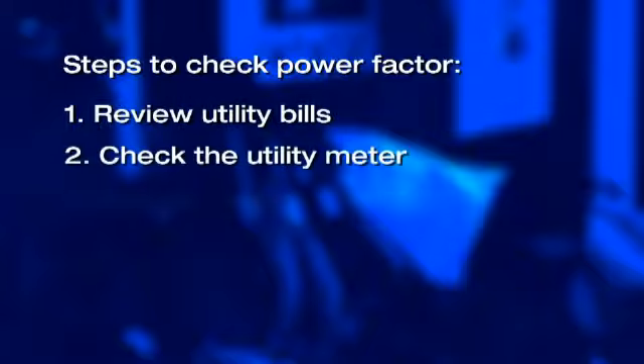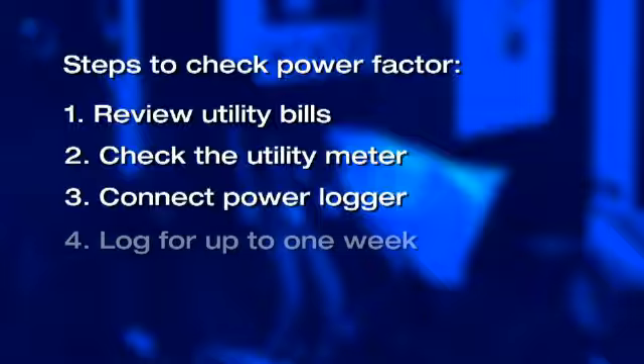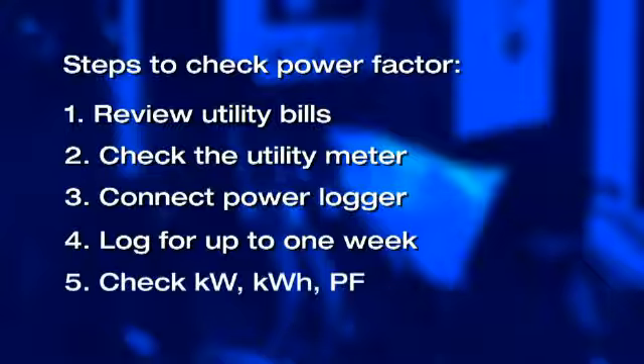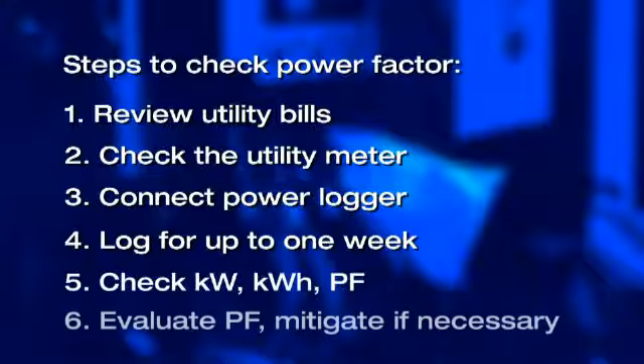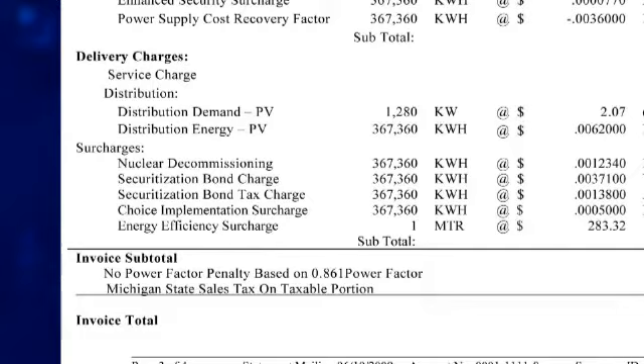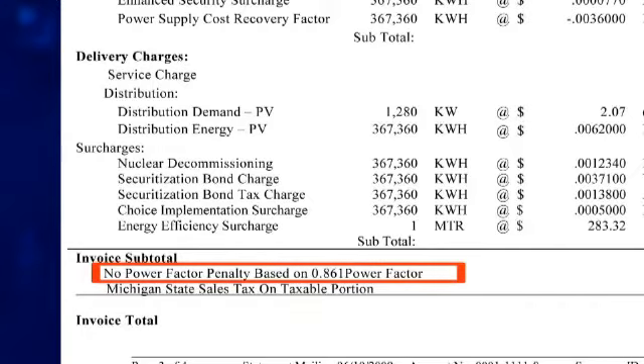Some of the steps we will take today to help you keep your utility bill low by using power factor checks are: review utility bills, check your utility meter, connect the power logger, log for up to 1 week, check for kW, kWh, and power factor, and last, evaluate your power factor and mitigate if necessary. This is how much you can save every month if you use the Fluke 1735 power logger to monitor and manage power factor in your facility.